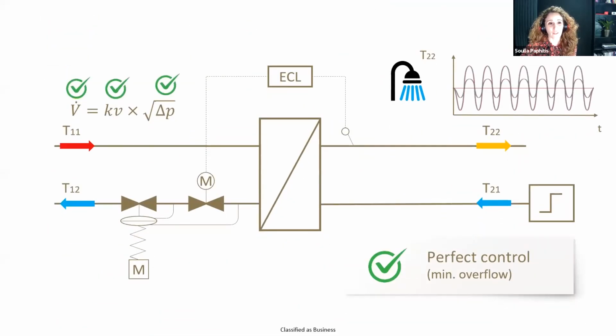Yeah. So just going back over a bit of the theory here. So let's see how we can achieve this perfect flow in a substation. The equation that you've got on the left there requires us to control the kV and differential pressure in order to achieve a perfect flow. So without any valves in the substation, you're not looking at controlling anything at all. So the behaviour of the substation would be completely unpredictable. As we install a motorised control valve, we gain the ability to control the kV, which is the valve opening part of the equation there.